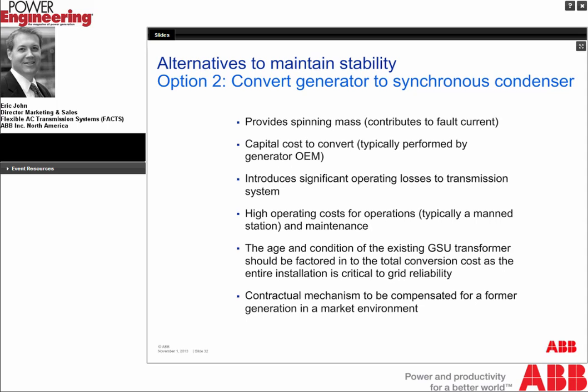It can also be problematic if you're in a physical location where substation breakers are close to a limit as far as what their clearing capability is. And I'll come back to this point on the next one, but the spinning mass can either be a benefit or a drawback technically.